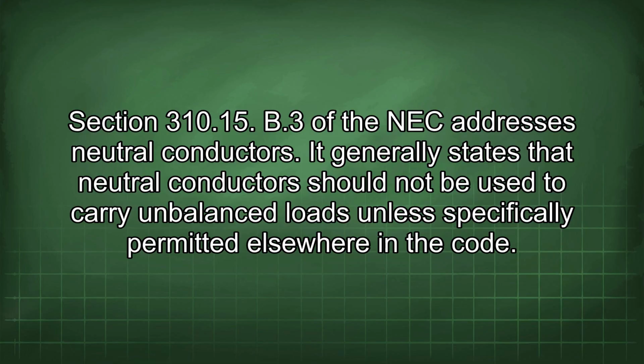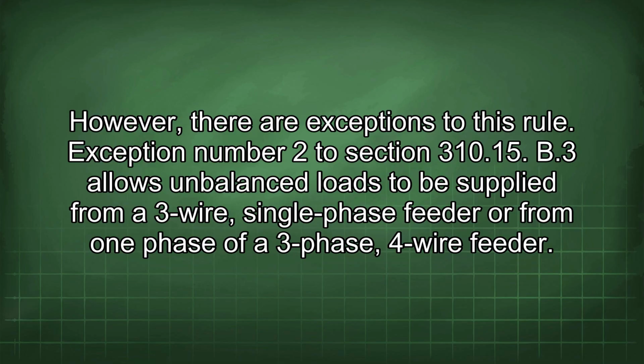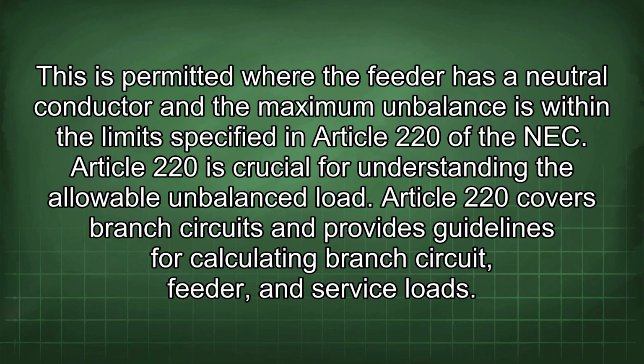It generally states that neutral conductors should not be used to carry unbalanced loads unless specifically permitted elsewhere in the code. However, there are exceptions to this rule. Exception number 2 to section 310.15 B3 allows unbalanced loads to be supplied from a 3-wire, single-phase feeder or from one phase of a 3-phase, 4-wire feeder. This is permitted where the feeder has a neutral conductor and the maximum unbalance is within the limit specified in Article 220 of the NEC.